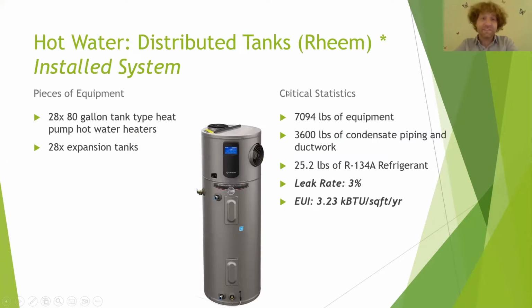So the first system we analyzed was distributed tanks. Out of all the heat pumps, these have been around the longest. This was actually the only system we had at the time to do heat pump hot water heating for this building. But it's relatively simple because you don't have a circulation loop or anything like that. It's just a heat pump per one or two apartments, a package unit. Doesn't use a ton of refrigerant, and doesn't leak a whole lot.